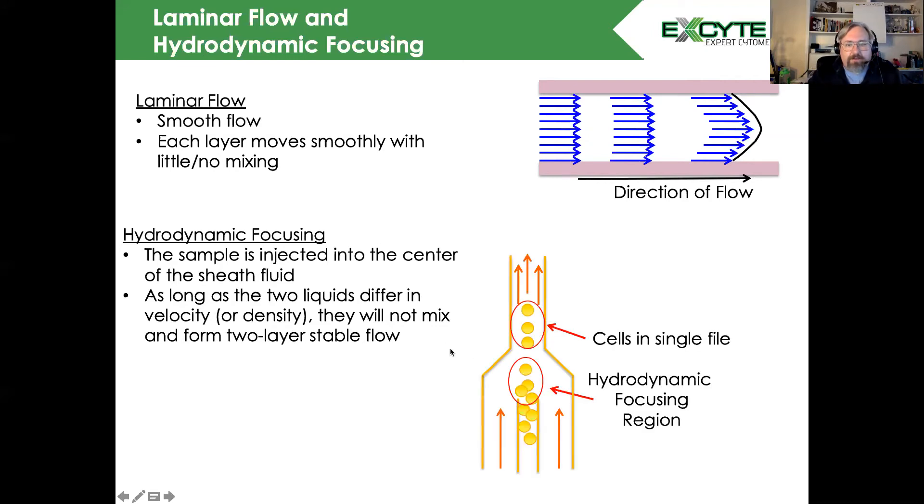Here is a typical flow cell. We have our sample being injected here. Our sheath fluid is running in this direction in red, and as the sample is injected, you'll see it's coming in as a blob. With hydrodynamic focusing, we force the cells along the velocity axis to pass single file by the laser intercept.